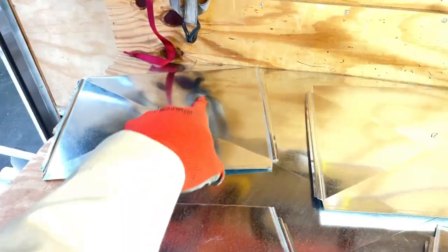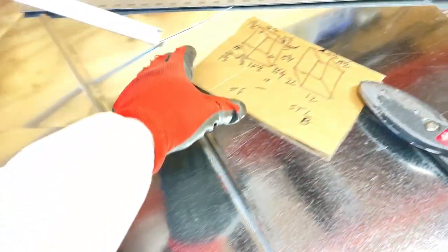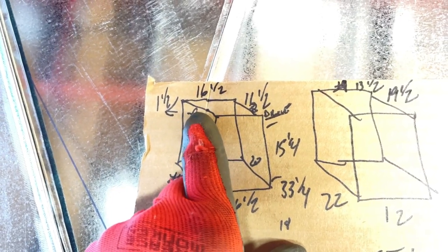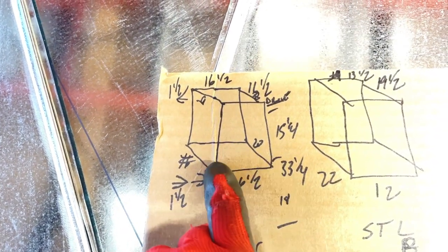Well, I have an update. I screwed up. The top of my plenum, if you can understand that, is 16.5 by 16.5, and he's got the ears on it for the drive. When I do my metal, I go off the bottom or the biggest size and add my 2 inches. Well, I forgot to take my measurement up here, and I just went ahead and did my thing. I could not have used this because I would have lost my inch if I would have cut this off and retraced. So I had to redo it. So there it is. I just got to cross break it, but yeah, it is what it is.